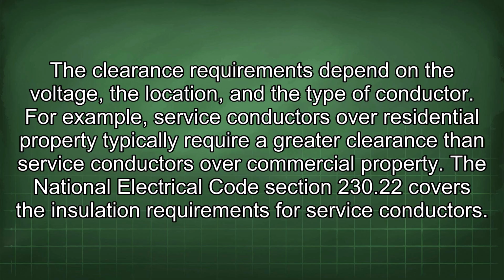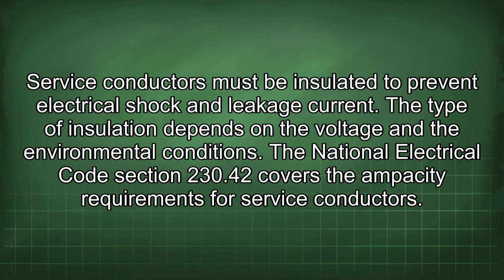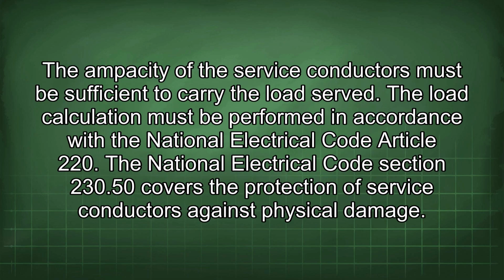The National Electrical Code Section 230.22 covers the insulation requirements for service conductors. Service conductors must be insulated to prevent electrical shock and leakage current. The type of insulation depends on the voltage and the environmental conditions. The National Electrical Code Section 230.42 covers the ampacity requirements for service conductors. The ampacity of the service conductors must be sufficient to carry the load served. The load calculation must be performed in accordance with the National Electrical Code Article 220.